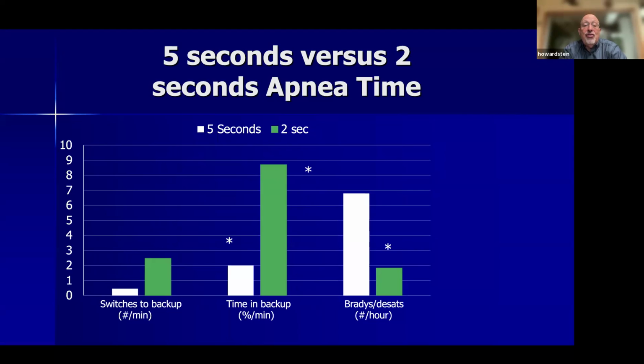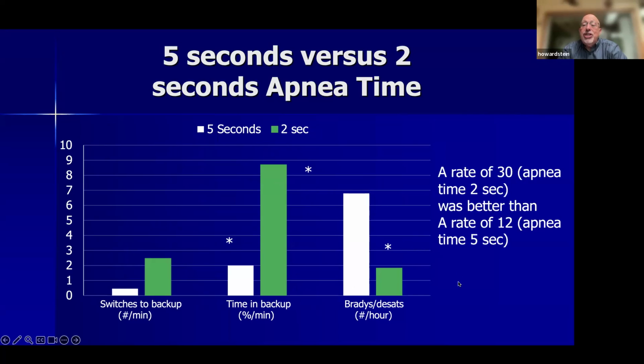But even in 2-second apnea time, they're in backup less than 10 seconds, less than 10% of that minute. So they're still getting 56 seconds out of every minute in spontaneous respiratory effort. But the key here is when they were on a 5-second apnea time, they had far more bradys and desats per hour than when they were on a 2-second apnea time. And what we showed was a rate of 30 was better than a rate of 12, which I don't think surprises anyone, because if you've got a baby that you're ventilating with a rate of 12, that baby is just not going to be clinically very stable.